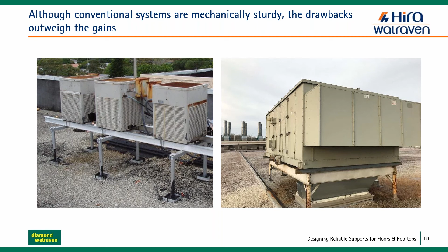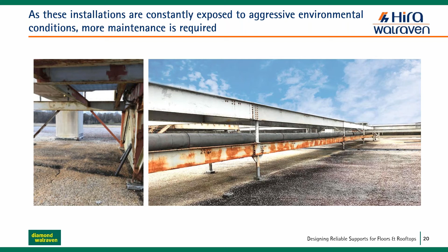We can see in this slide some examples of the traditional way of installing outdoor units or air handling units on the roof using I-beams, C channels, or U profiles, welding and bolting them on the ground. All these installations are constantly exposed to aggressive environmental conditions, as we discussed, so more maintenance is required, like repainting or galvanizing on site. This is costly and adds additional work, so we see loss of metal integrity over time with increased maintenance costs, equipment downtime, and asset depreciation.